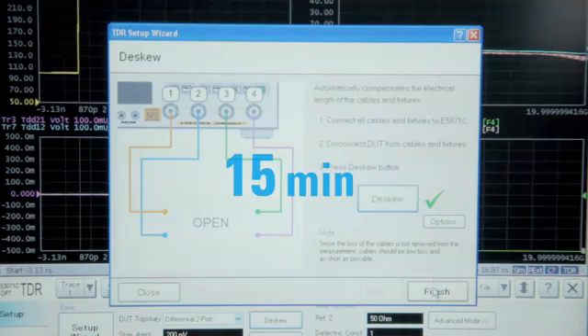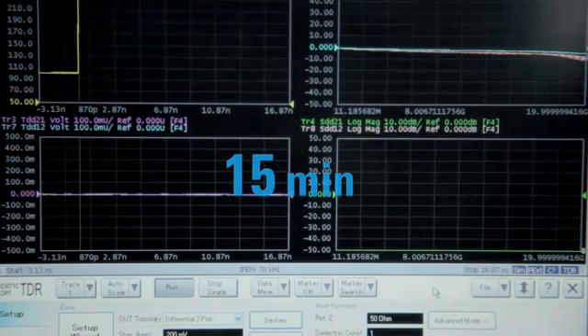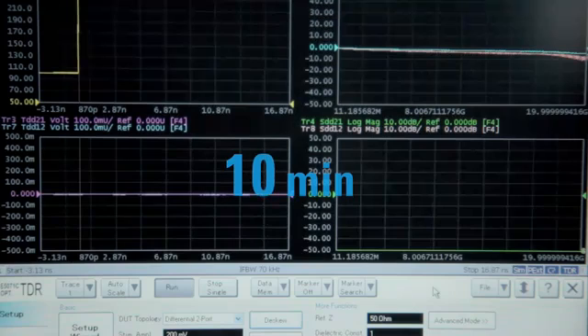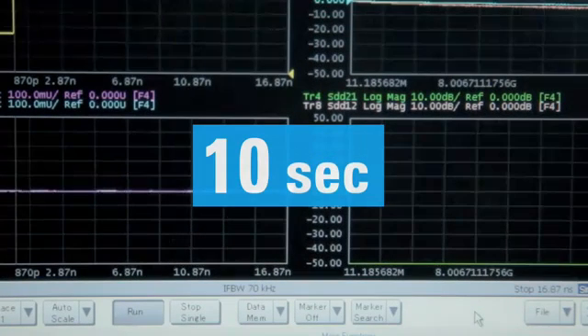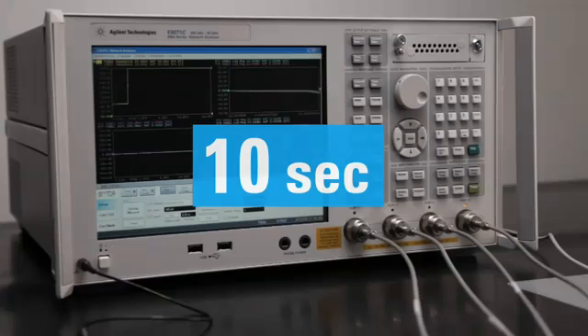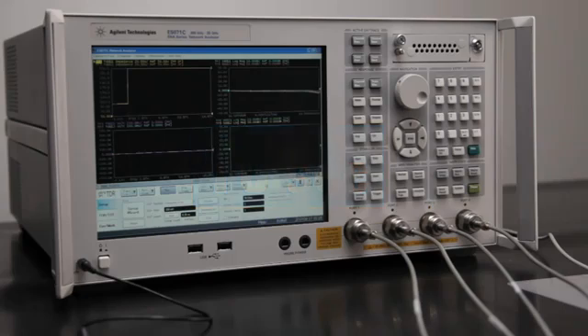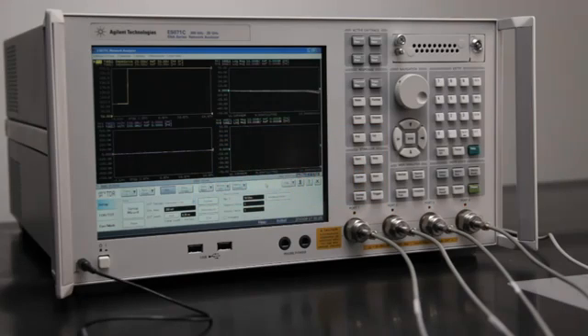Using an ENA Option TDR, a procedure which took 15 minutes on an oscilloscope took a mere 10 seconds. That's all the time it takes for even a complete beginner to acquire the same results you'd get with a conventional instrument.